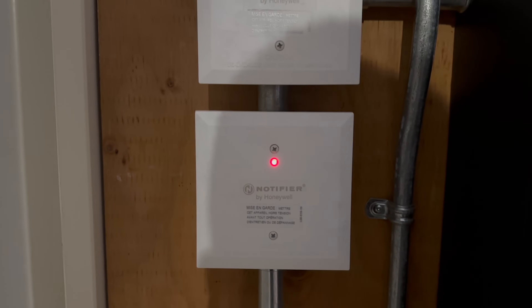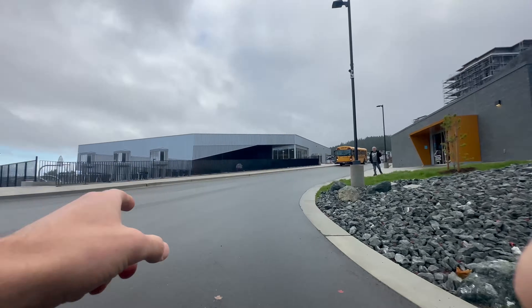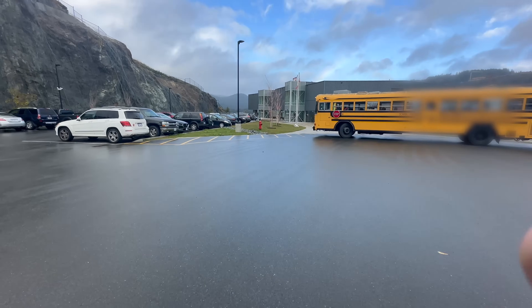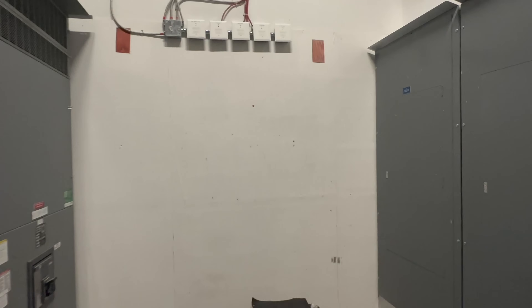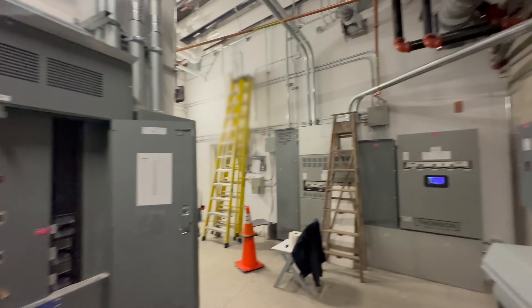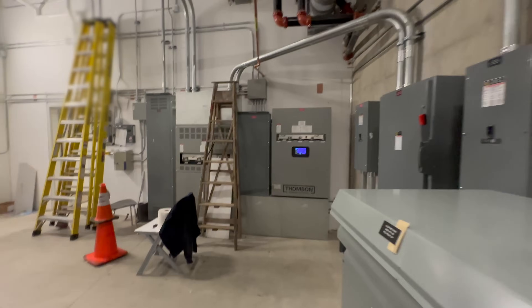Fire alarm generator module is active. The central plant — that's the elementary school and that's the middle school. They put outside wall packs on emergency power here, but not the parking lot fixtures. Middle school is on generator power, so about half of the corridor lighting is on. Transfer switches.